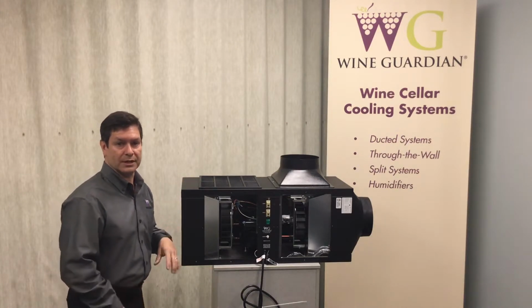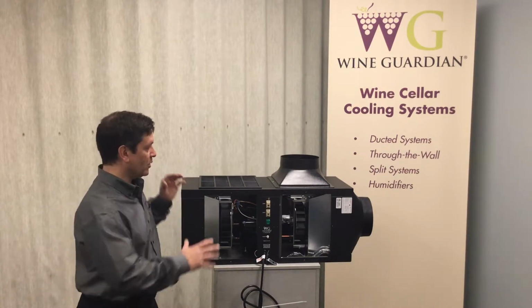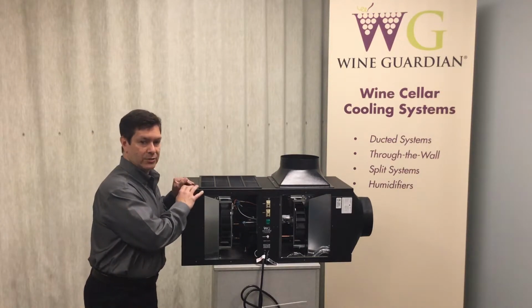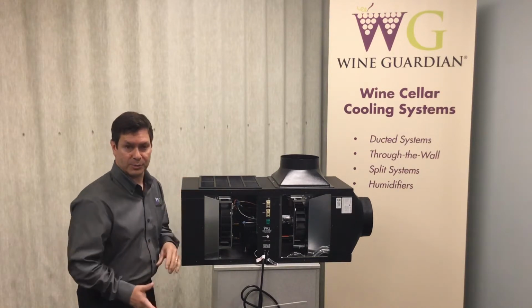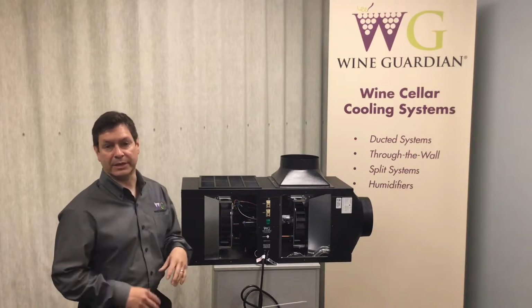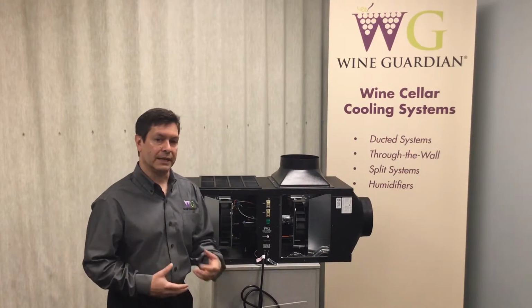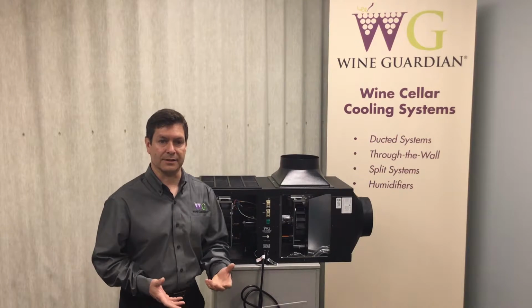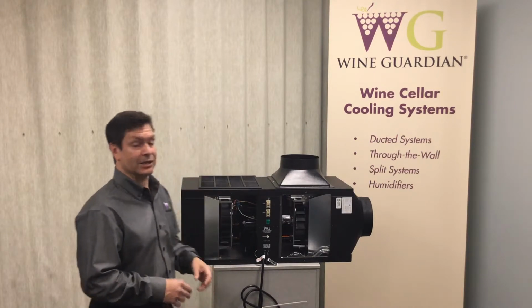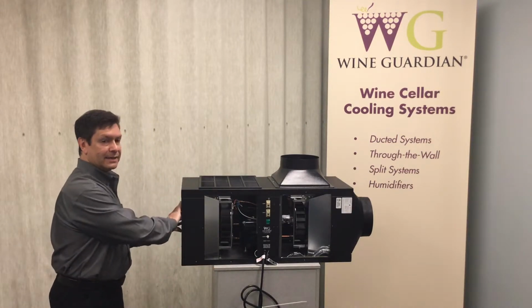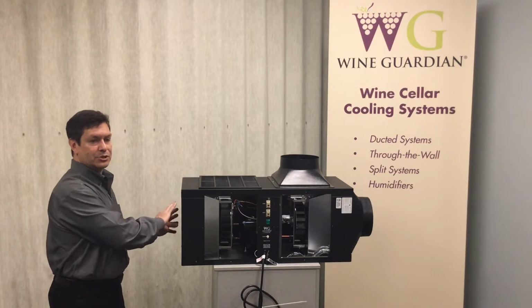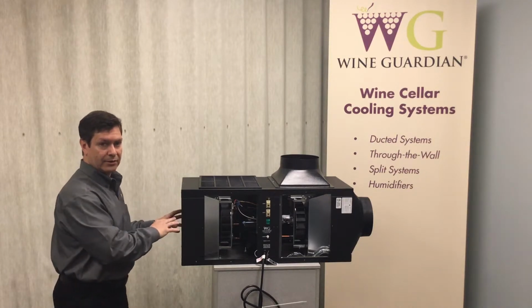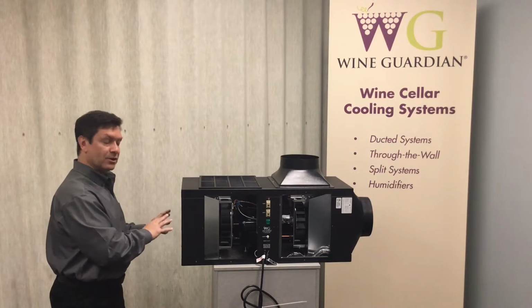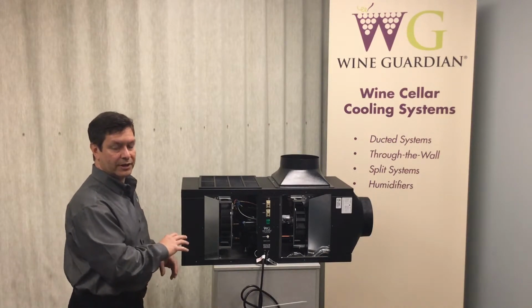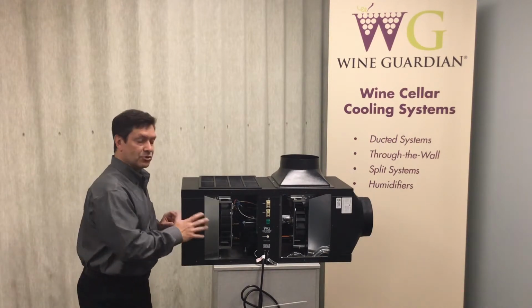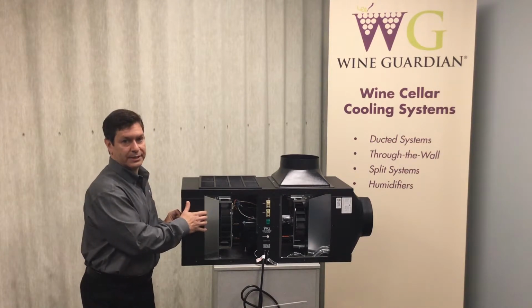So where is it used? You have to look at where you're going to physically mount the cooling unit. Okay, if it's in a crawl space or if it's in a mechanical room that is very small and you can't vent it correctly, and you have to bring in air from outside, you have to consider the temperatures year-round of that air. If this air is going to be below 40 degrees Fahrenheit, then you want to make sure that this system has low ambient protection on it.